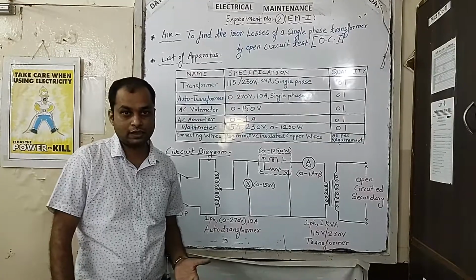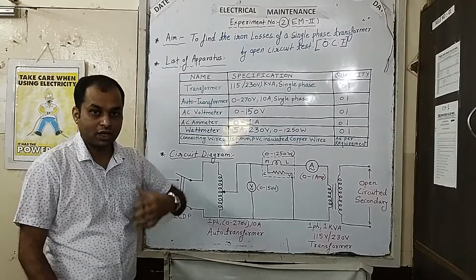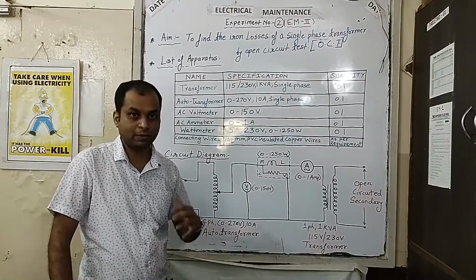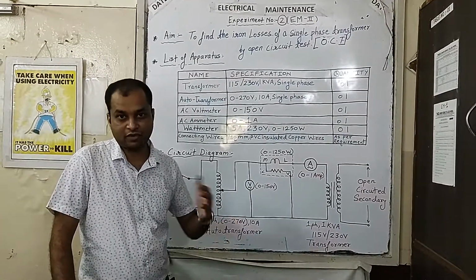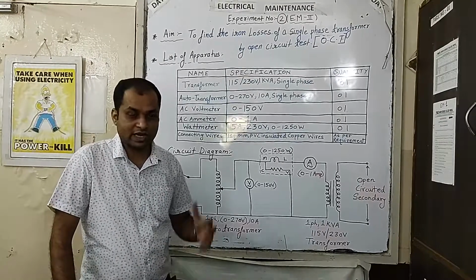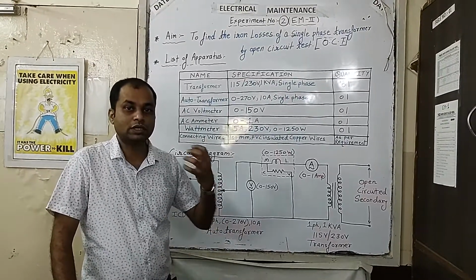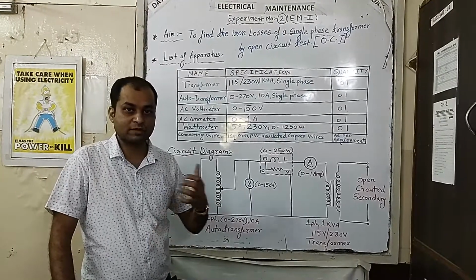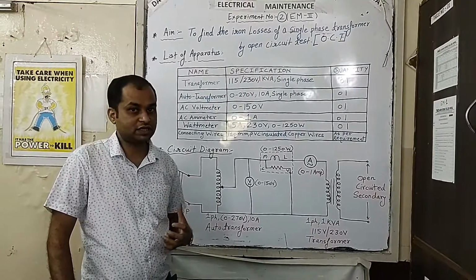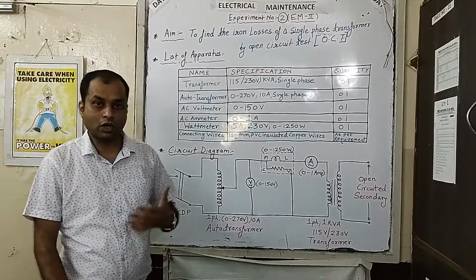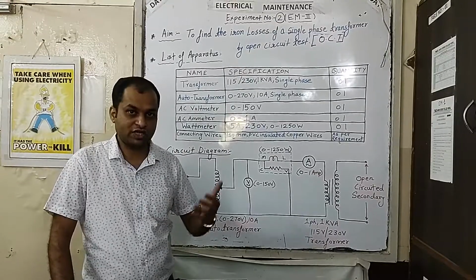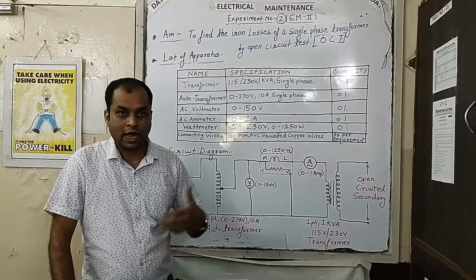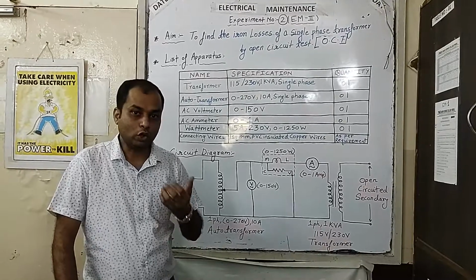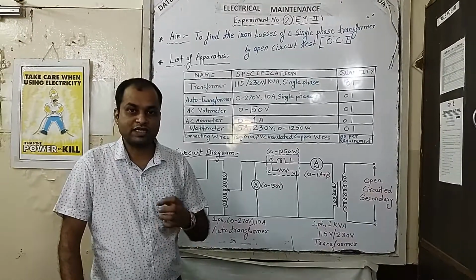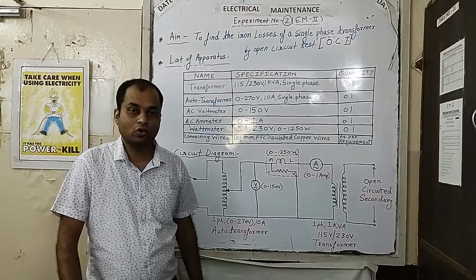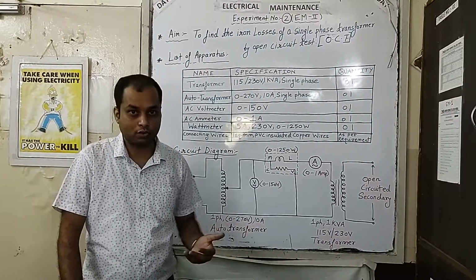As we have studied in the theory, in open circuit test we apply rated voltage across the primary of a transformer and the secondary winding we have to keep open. So as the secondary winding is opened, the current drawn by the transformer across the primary winding is the current which is utilized to supply the losses taking place in the core, which are in the form of hysteresis and eddy current losses. So transformer will absorb very low current from the supply having very small magnitude just to supply the core losses and secondly to magnetize the core.